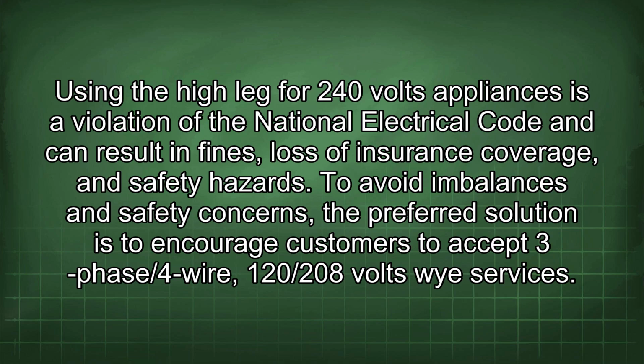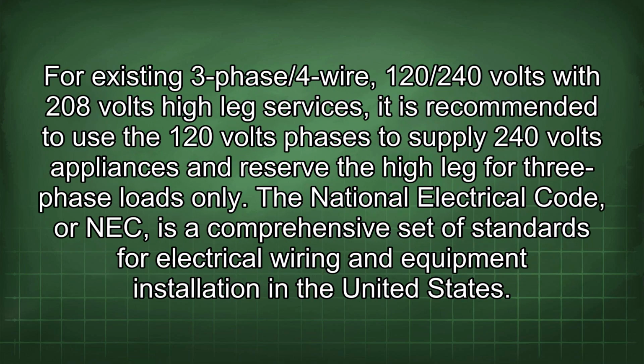To avoid imbalances and safety concerns, the preferred solution is to encourage customers to accept 3-phase/4-wire, 120/208 volts Y services. For existing 3-phase/4-wire, 120/240 volts with 208 volts high leg services, it is recommended to use the 120 volts phases to supply 240 volts appliances and reserve the high leg for 3-phase loads only.